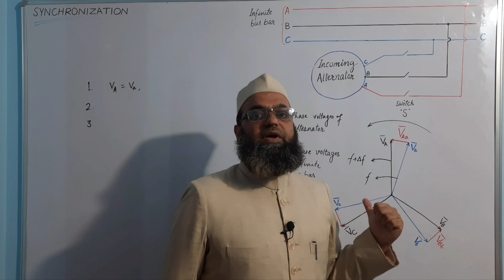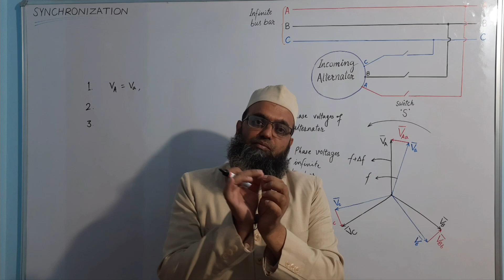So if phase sequence is same, which must be there under condition number 3, then whenever VA coincides with this VA, VB will coincide with this VB, and VC will coincide with this VC. And this is the moment when switch S must be closed. At that moment, the potential drop between these 2 points, either side of this switch, will be 0. The 2 points will be at the same potential.